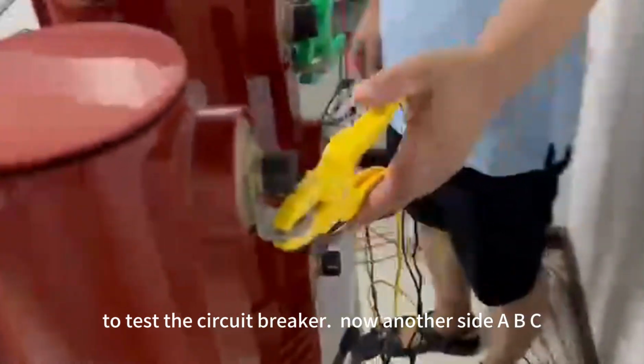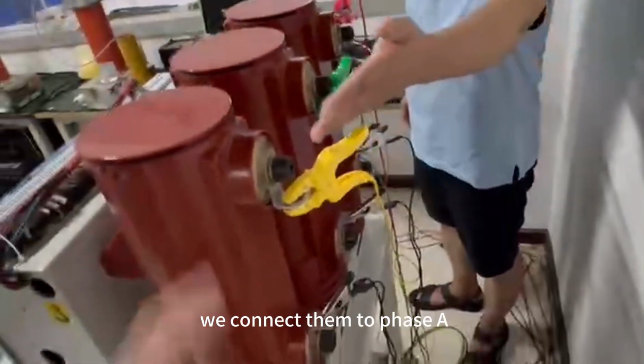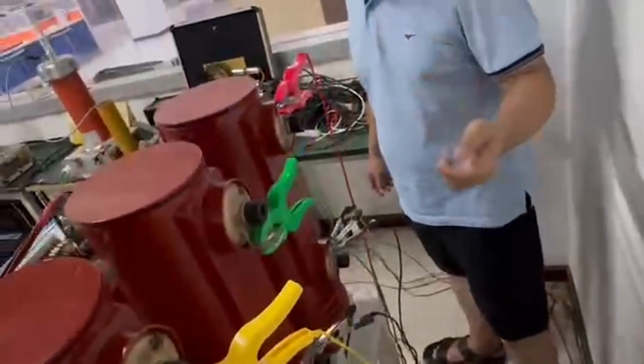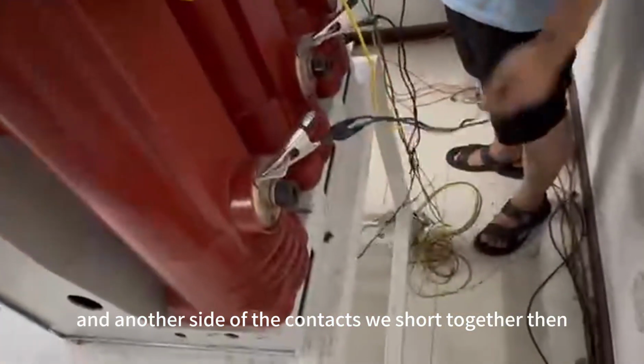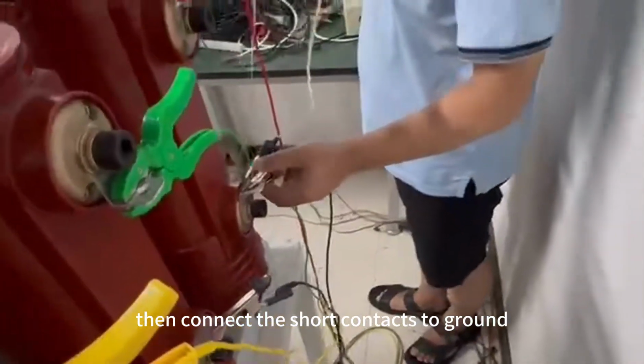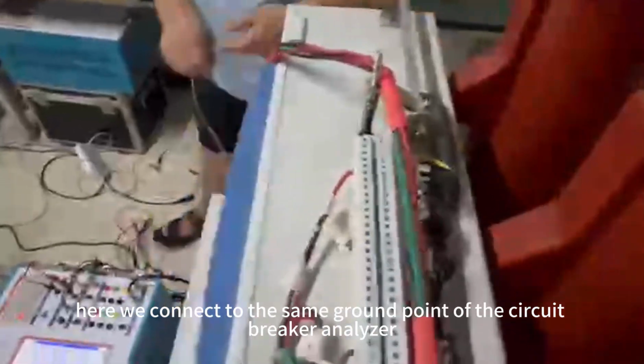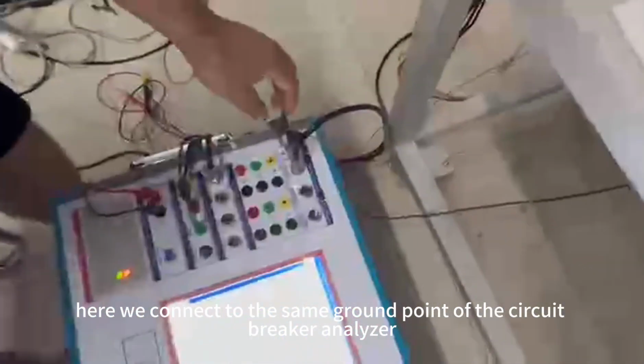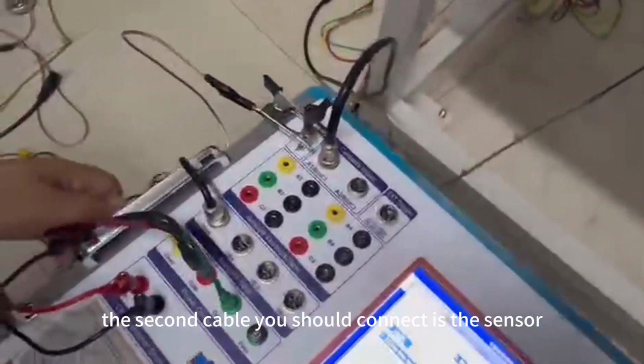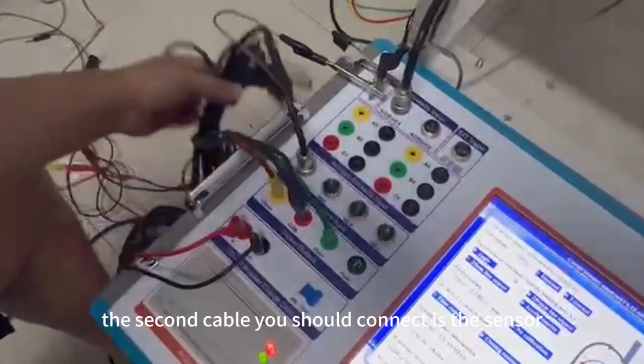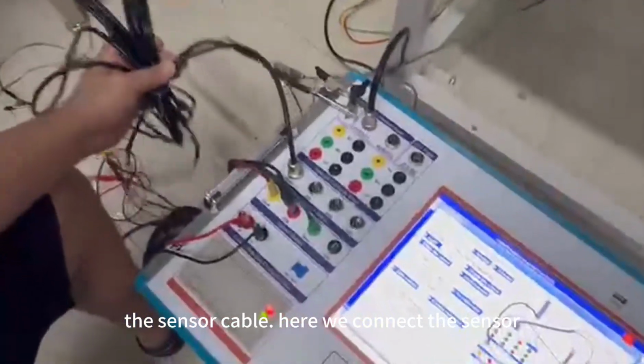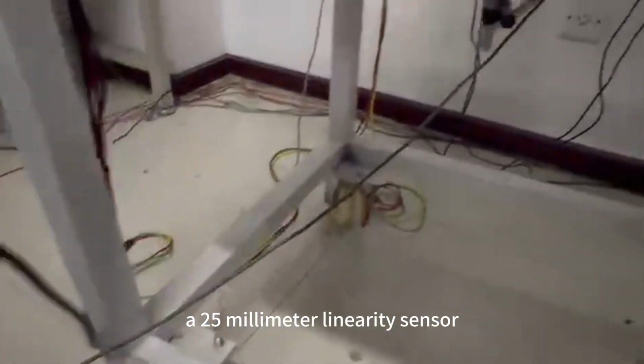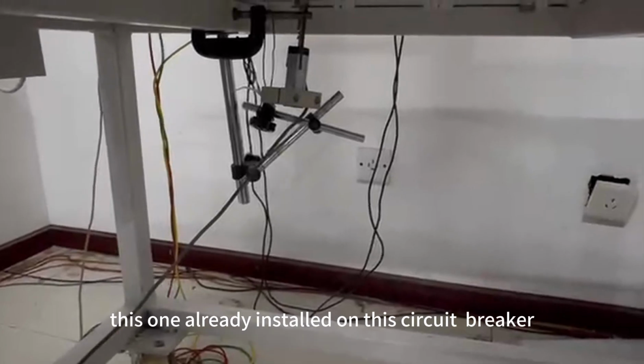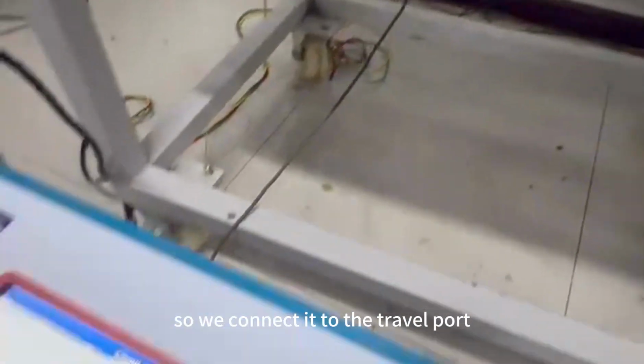Now on the other side, A1, B1, A, B, C, we connect to phase A, phase B, phase C of the circuit breaker. And the other side of the contacts we short together. Then connect the short contacts to grounding. Here we connect to the same grounding point of the circuit breaker analyzer. The second cable you should connect is the sensor cable. Here we connect a 25 millimeter linearity sensor. This is already installed on this circuit breaker, so we connect it to the travel port.